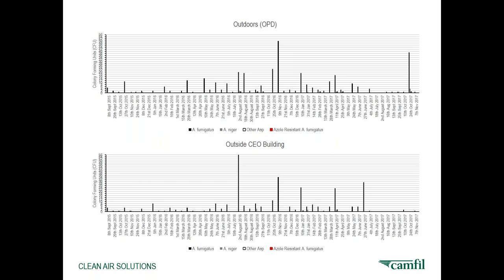We then looked at the different areas of the campus, and in particular outside where there are contaminants floating generally in the air from the construction sites potentially, but also being an inner city site with significant traffic movement, normal construction activities that will be happening in the city dwellings. And we took studies every 2 weeks to identify the actual type of Aspergillus numbers in volume. I must say the particle count on the previous baseline study is related to the volume and numbers of particles, not specific to the actual type of particles, where our own studies carried out later looked at the actual type of particles and what was in those particles.